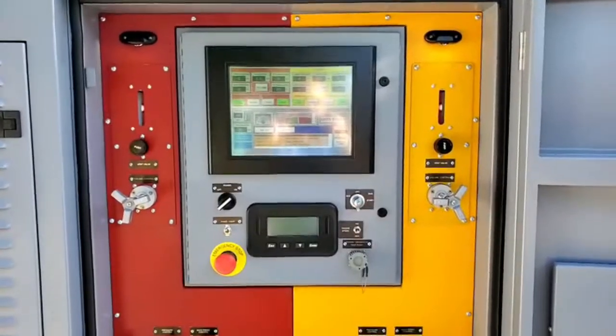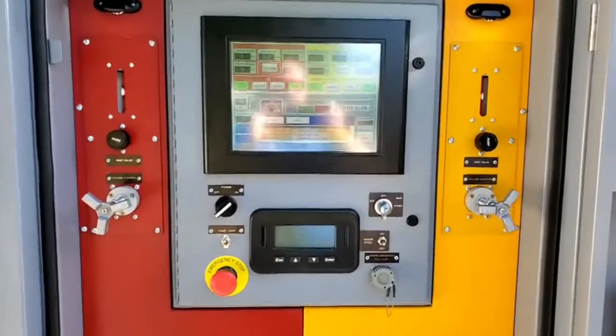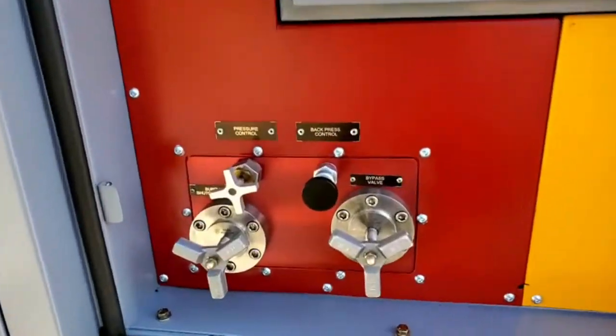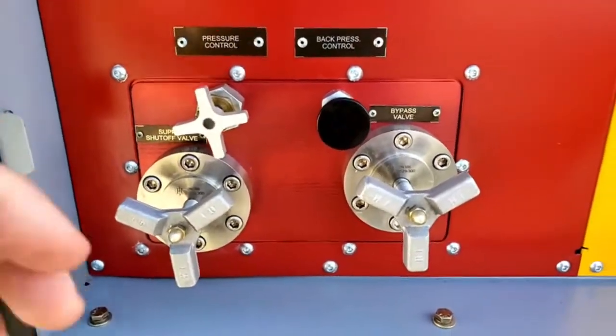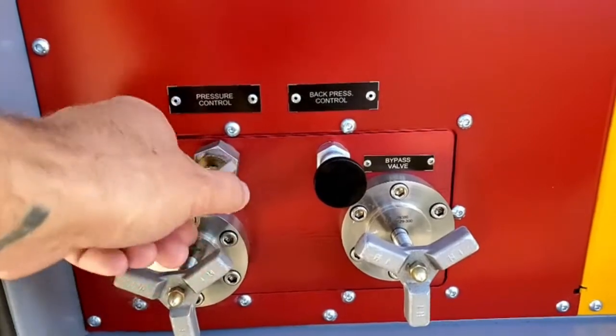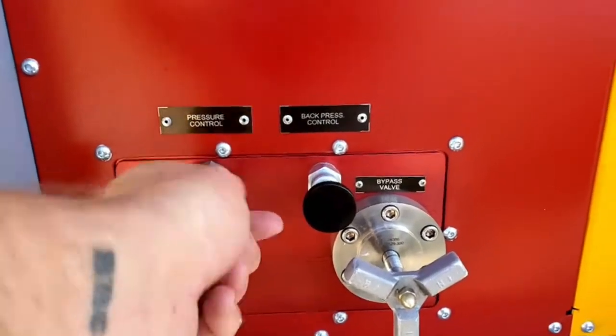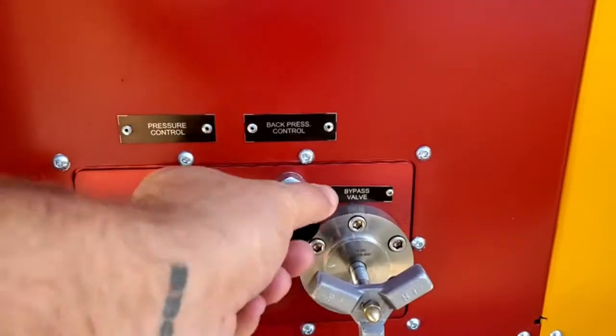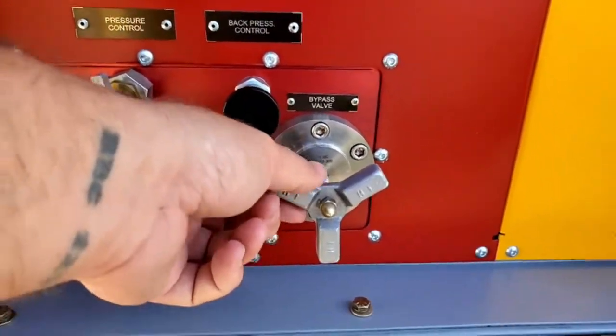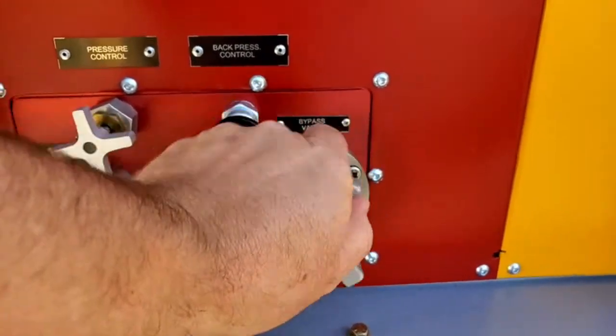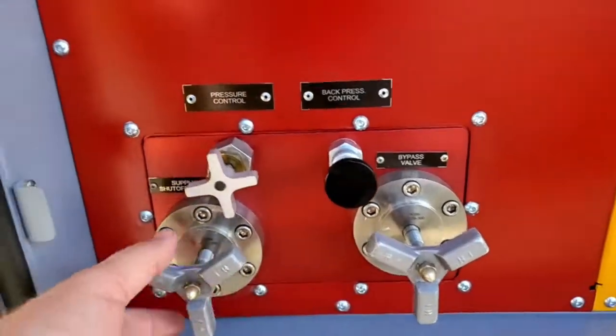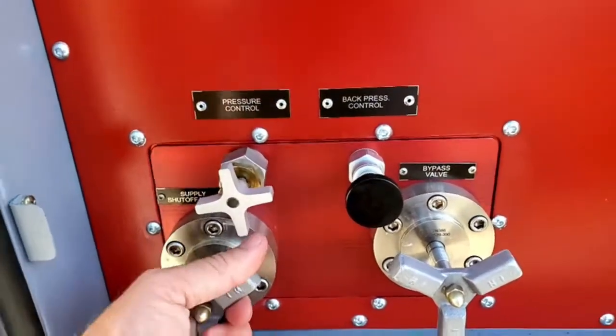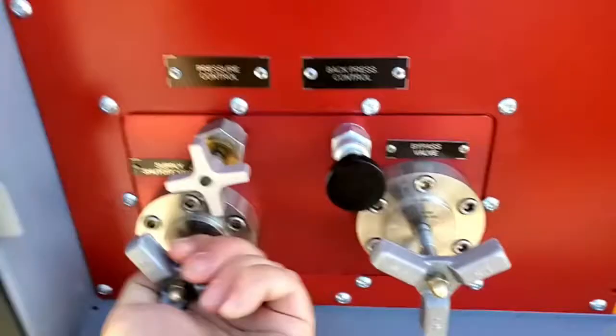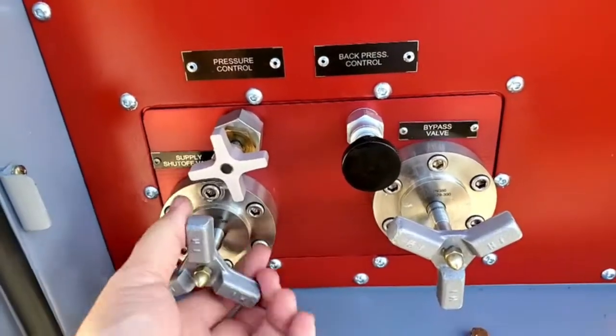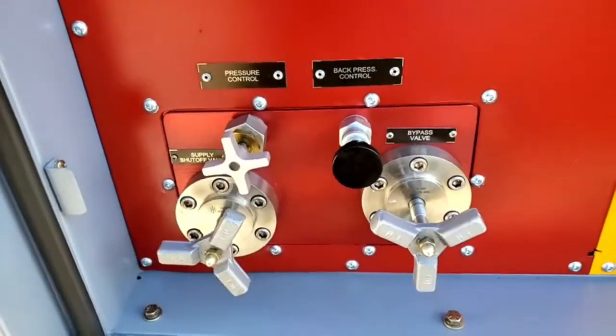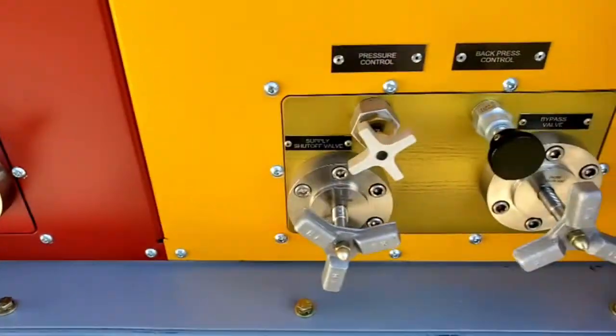So upon coming to the unit for operation, you want to make sure that your pressure control knob here is fully counterclockwise. Your back pressure control is fully counterclockwise. Your bypass valve is also fully counterclockwise. And your supply shutoff valve is fully clockwise. Now you'd set this up the same on both systems.